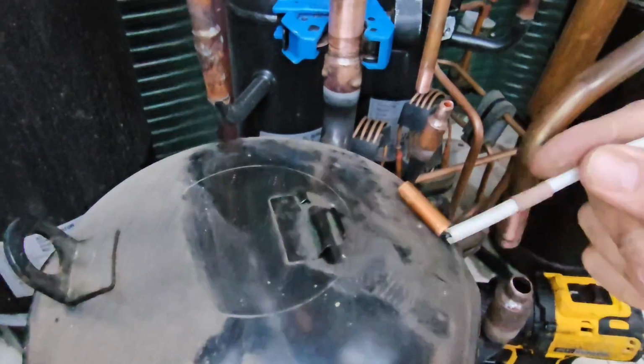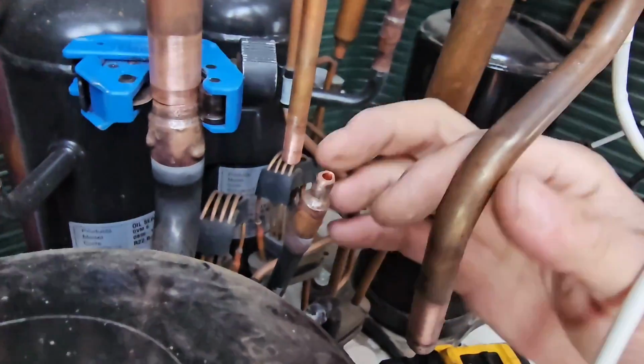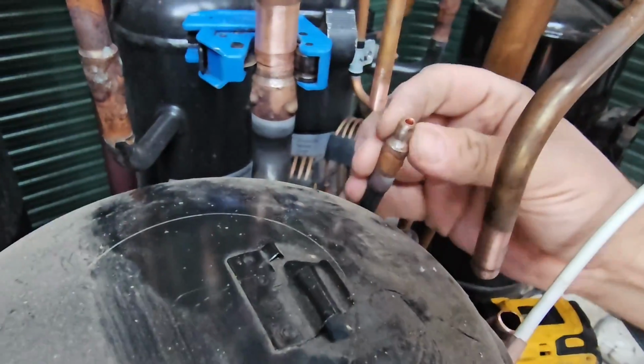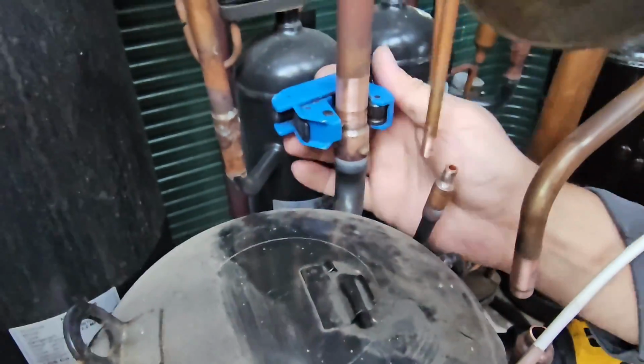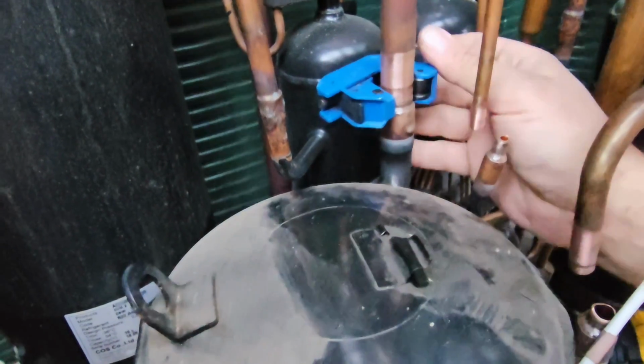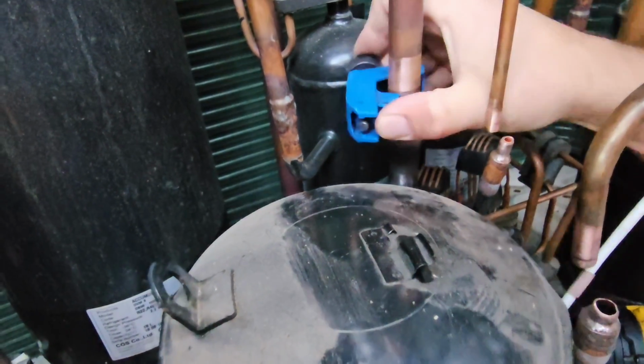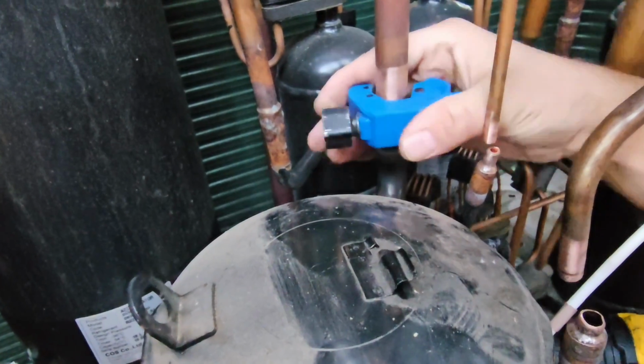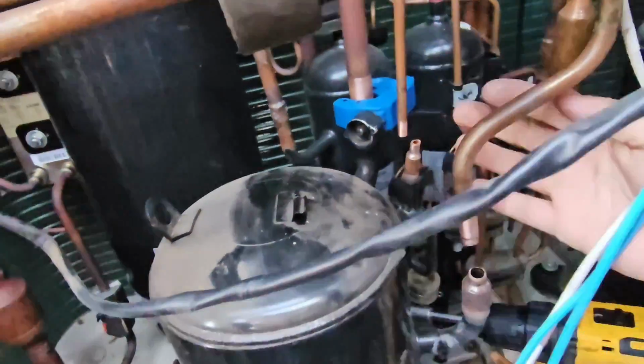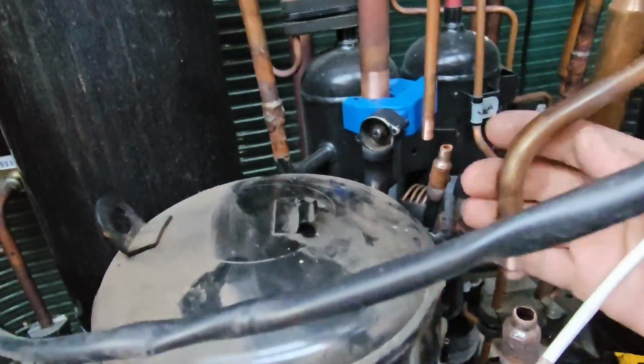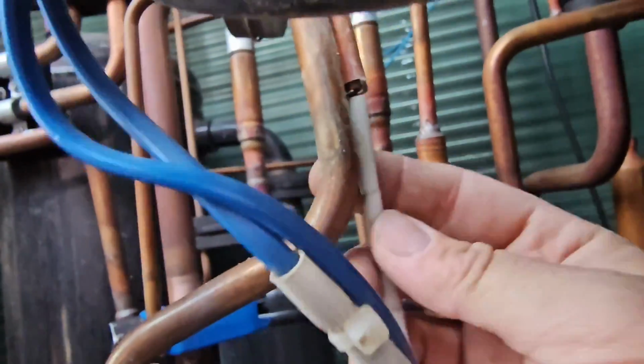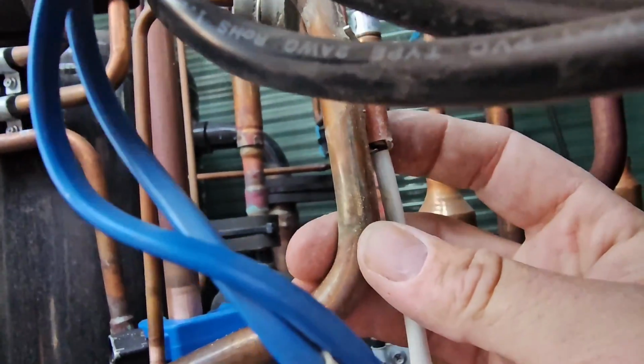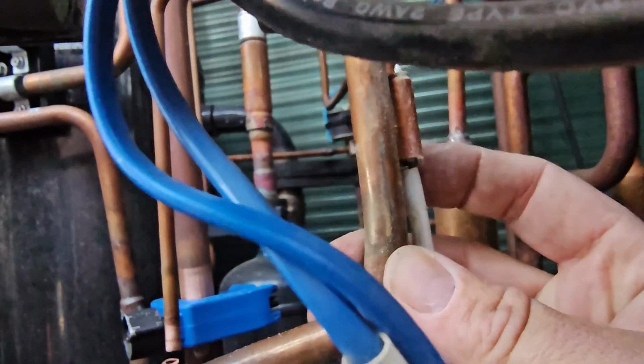Top thermistor has been removed. I have cut the discharge pipe and the oil return pipe. Now I've got 1 pipe left, and that is my low pressure pipe, or my suction pipe. So I'm going to keep cutting that. Another way you can identify the discharge line is there should be another sensor on that line. It's right here, and that's the discharge sensor. And that is another 200 kilo ohm sensor.